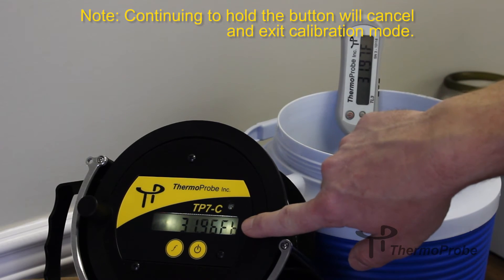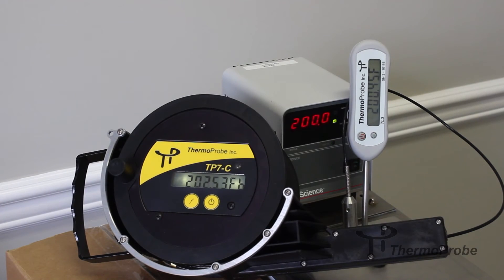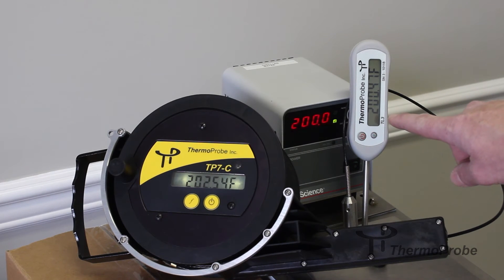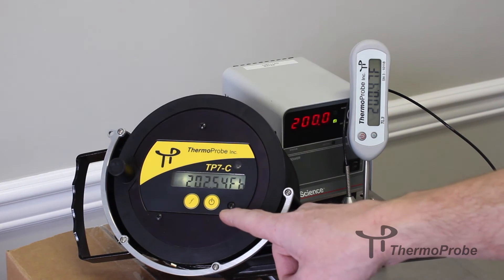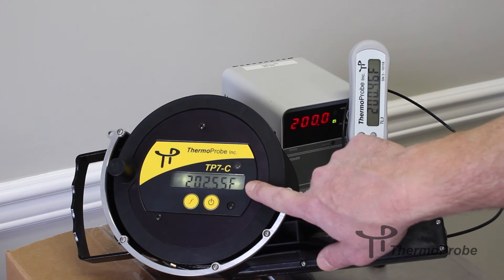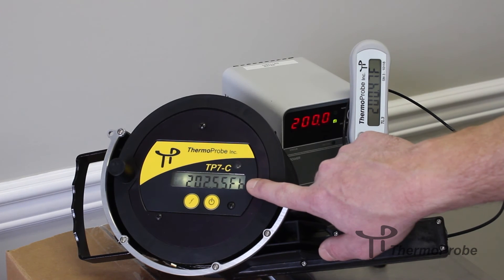Now we're showing a B, which means I'm looking for the next point. For our second calibration point, we've moved over to a 200 degree Fahrenheit bath. This can also be accomplished with a boiling pot of water or similar. The reference is reading 200.46–200.47 degrees Fahrenheit, and the gauging TP7 is showing 202.54. The B character is blinking to indicate this is the second point to be adjusted, and since we're only doing two points, this is the last point.